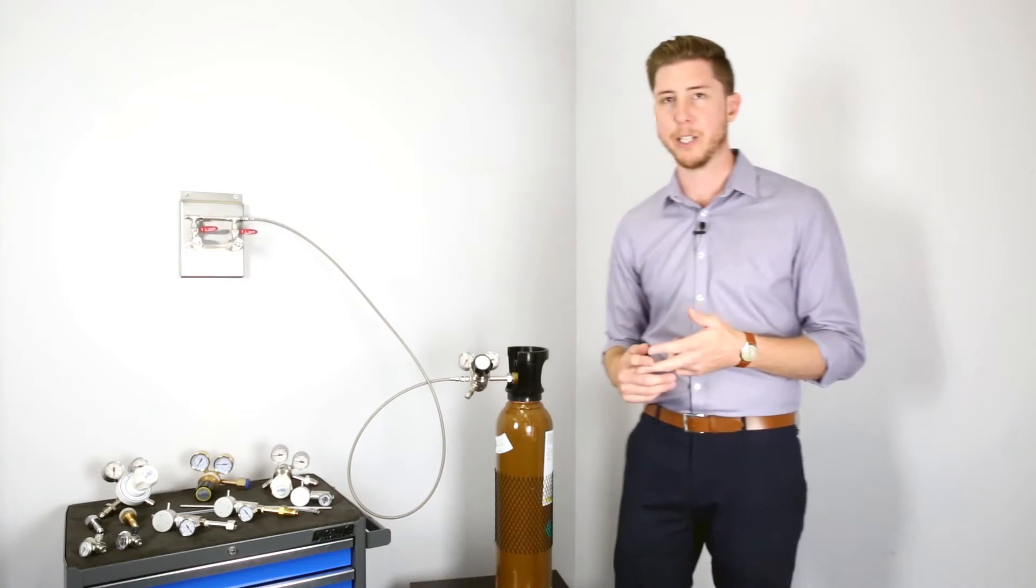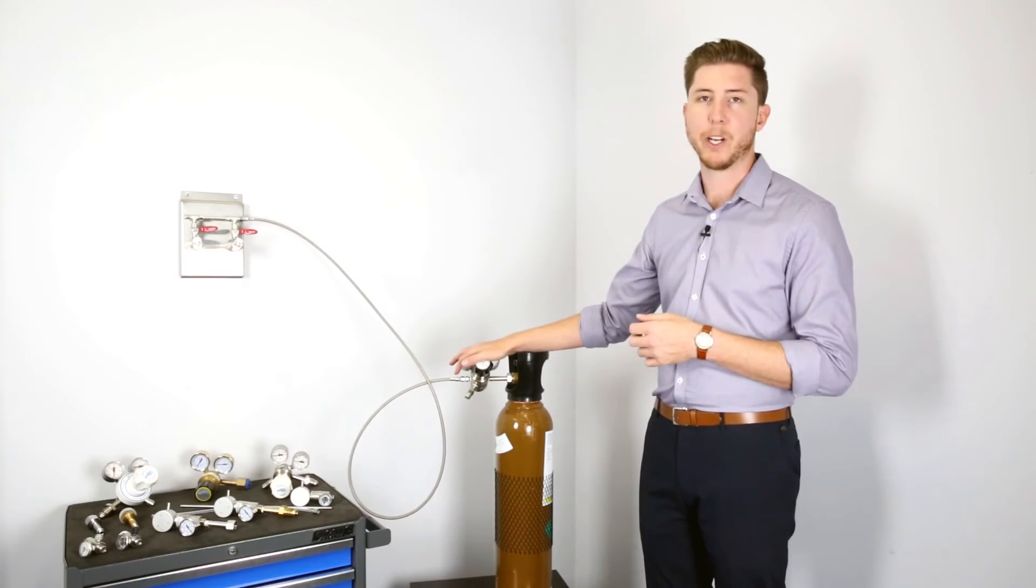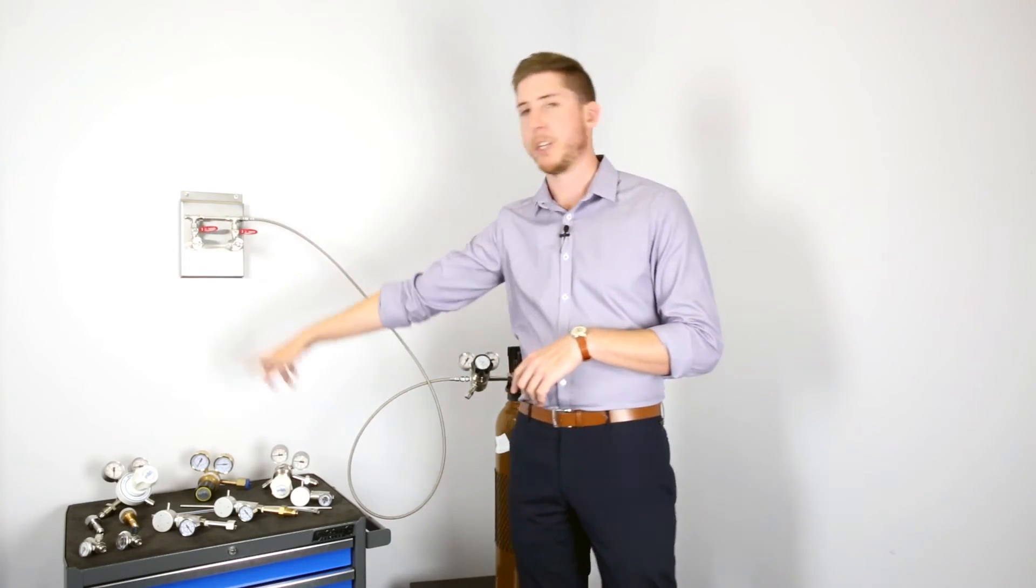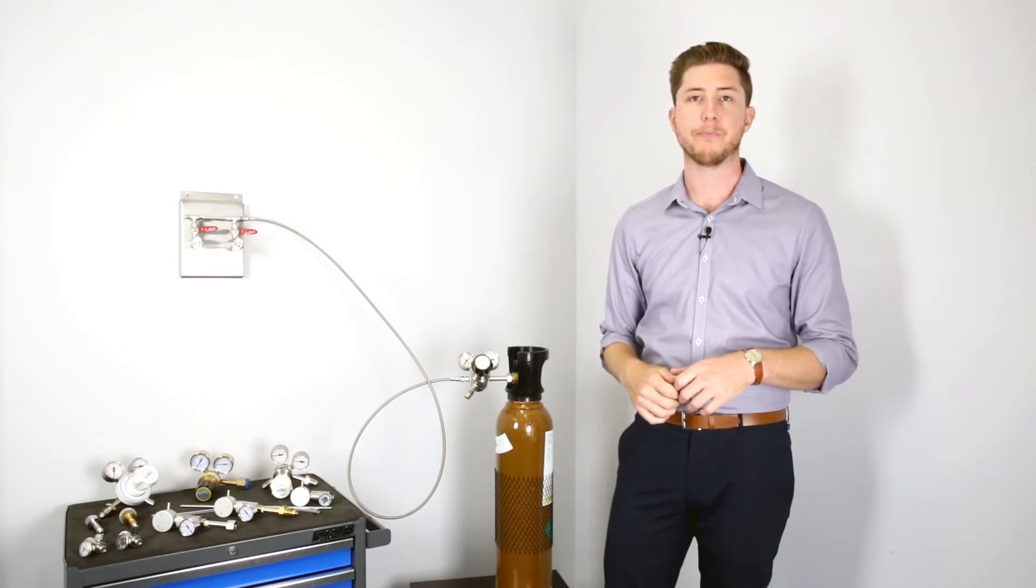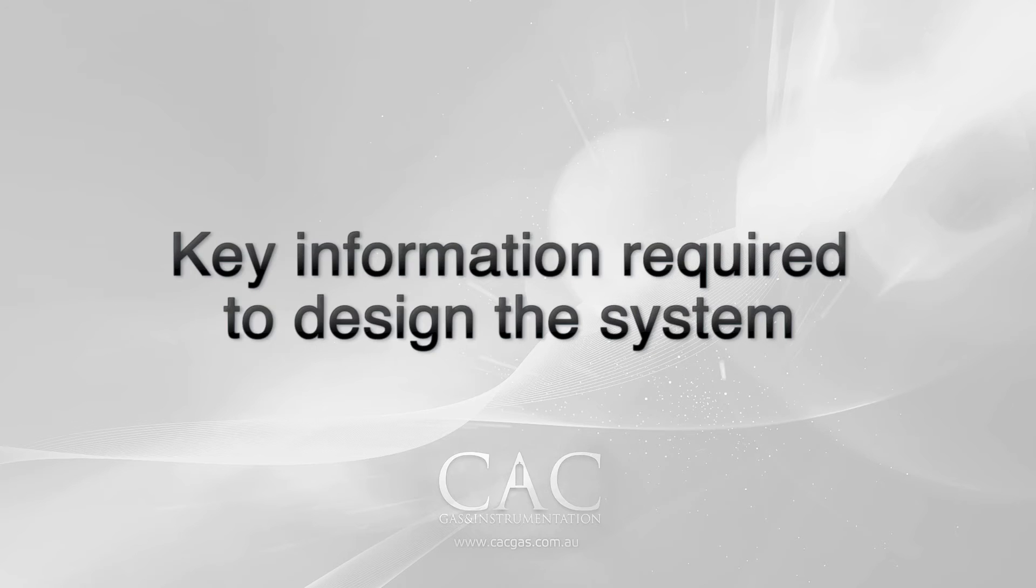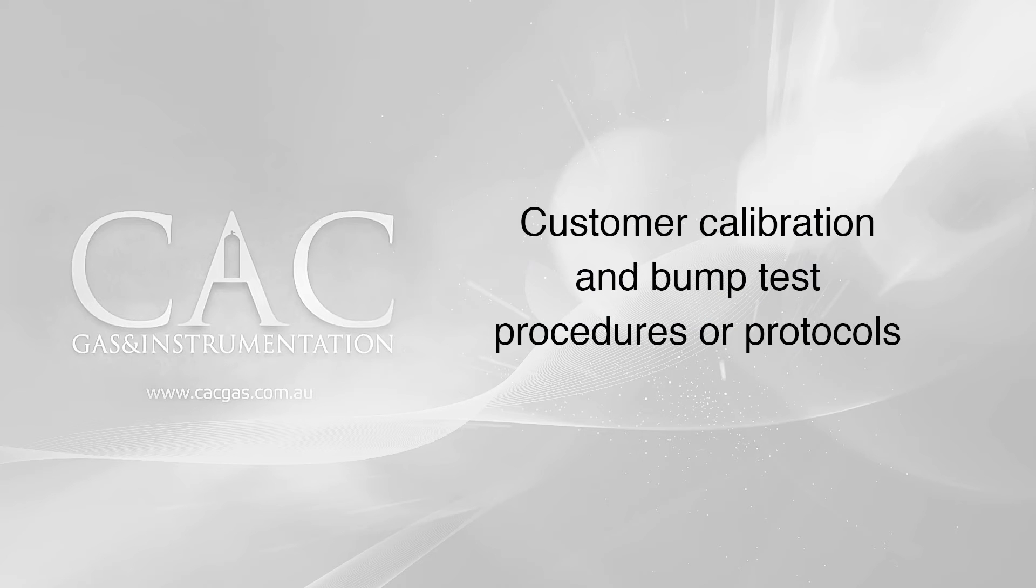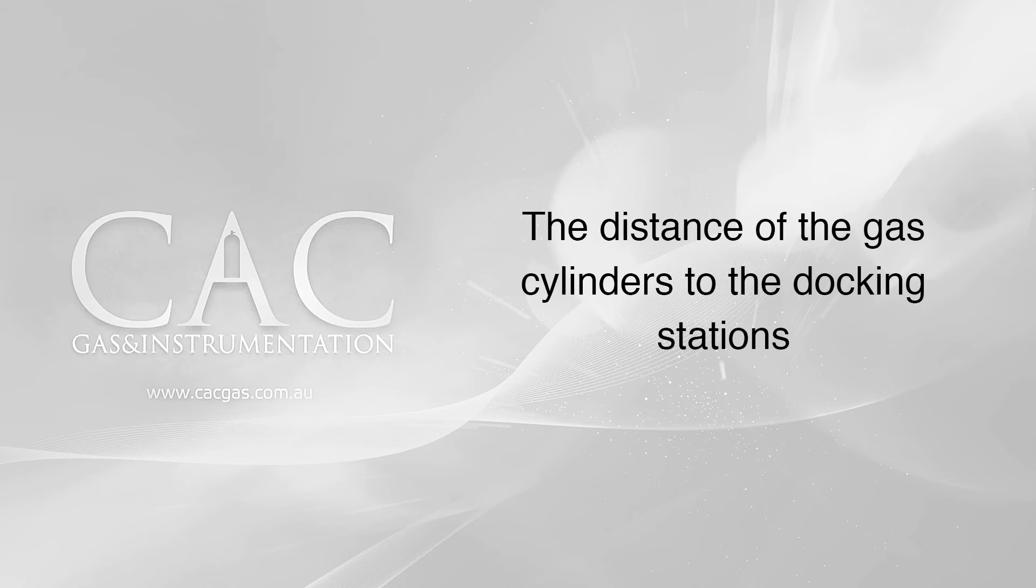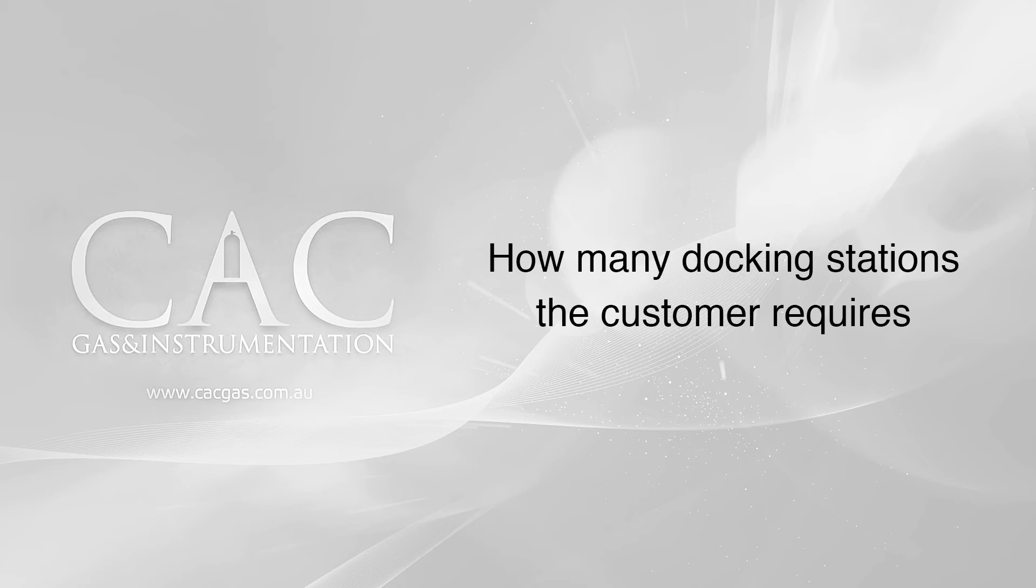A GDS consists of a gas cylinder, a cylinder mount regulator, some hosing and tubing to an outlet panel which can now connect down to your testing point or docking station. The key information that is required to design the system includes gas mixture and gas consumption detail, customer calibration and bump test procedures or protocols, the gas mixtures corrosive nature or non-corrosive nature, the distance of the gas cylinders to the docking stations and how many docking stations the customer requires.